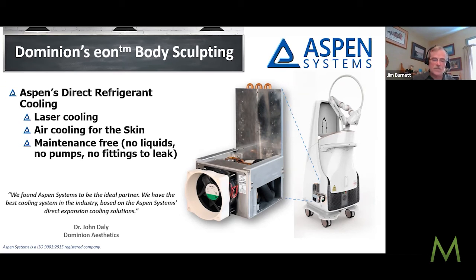As one of our laser customers put it, if I keep using my chiller, my maintenance guy needs to be a plumber, because the liquid lines are prone to failure—they're not nearly as robust as refrigerant lines. So not only would a chiller system be less efficient, it'd be higher maintenance, with liquid levels needing refills and lines more suspect. By going to direct refrigerant, it uses 25% less power, or maybe more, than a chiller would. And even a vapor compression chiller uses 4 or 5 times less power than a thermoelectric would under these conditions. So this is an example of something that couldn't exist without the miniaturization of refrigeration.